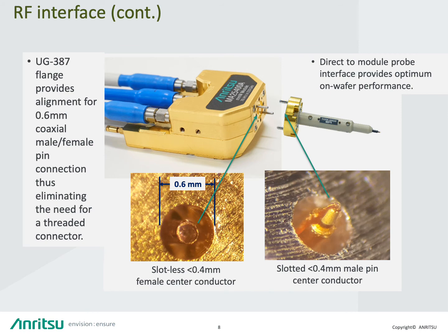The direction we took in connecting the probe to the module is to use the 0.6 millimeter connector, but to use a UG387 flange for the alignment. Using the flange that was designed for supporting 220 gigahertz connections gives us the repeatability and the alignment needed for these connections, but in this case we're using a male-female center pin connector.